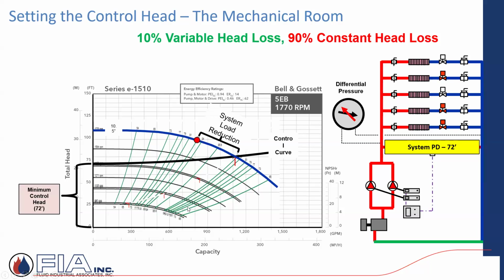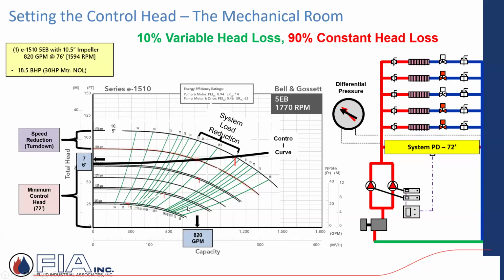You know, so it happens. Sometimes it's just a real world condition where I can't get the sensors remote. I'm going to use this in the mechanical room, but you're limiting that reduction, how low you can go with that variable speed. And you just want to recognize that. So it's certainly not the preferred. It's an option, but it's not preferred. You're missing out on operational conditions, or benefit, I should say, reduction.